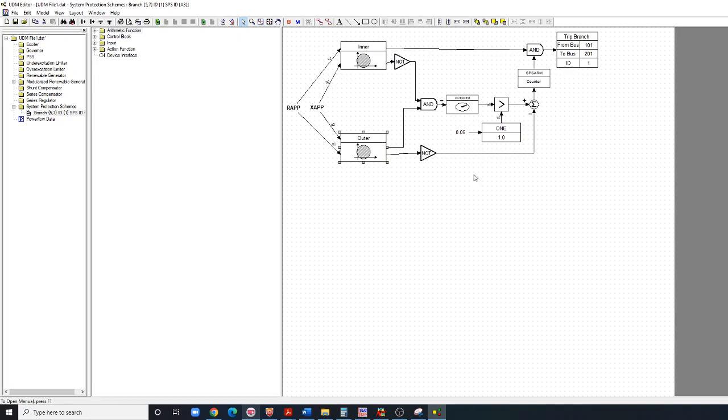If I find this particular condition, that means for this particular line, the apparent impedance is within the outer zone for more than 3 cycles and then touching the inner zone, I'm not going to trip any branch. I'm going to trip a generator.